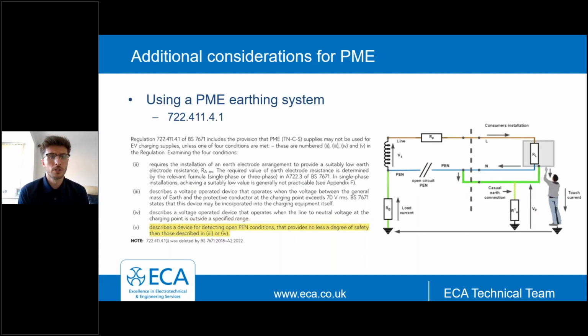So initially, we're going to look at additional considerations for a PME earthing facility. And this is covered within regulation 722.411.4.1. This regulation can be found on page 325 over onto page 326. It is relevant to PME earthing systems, where you're looking to put a charge point on a PME system, and this charge point is to be located outdoors, or is expected to be used outdoors.